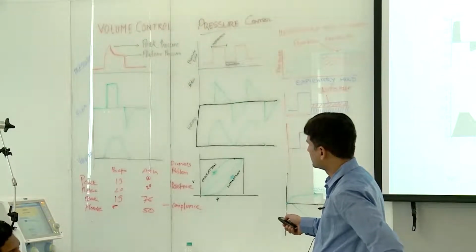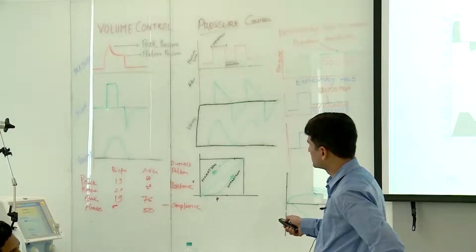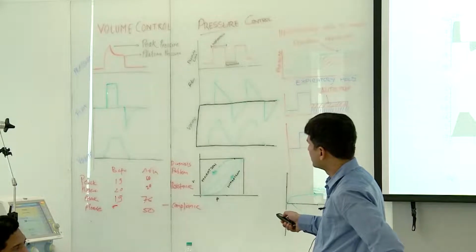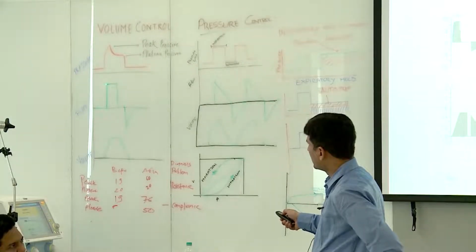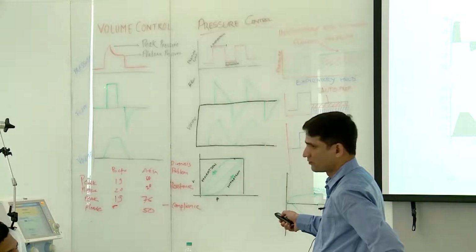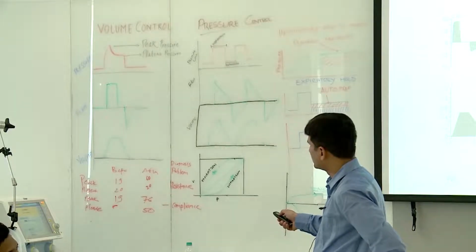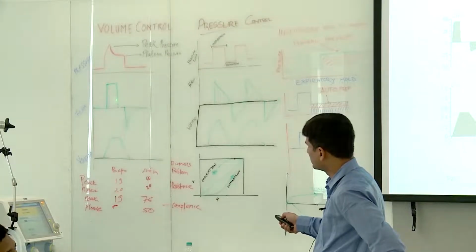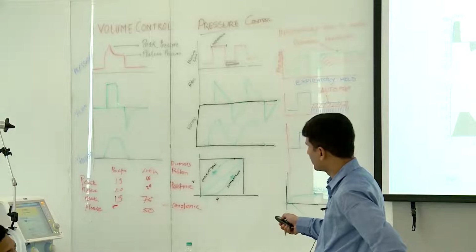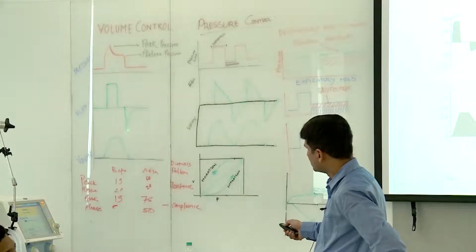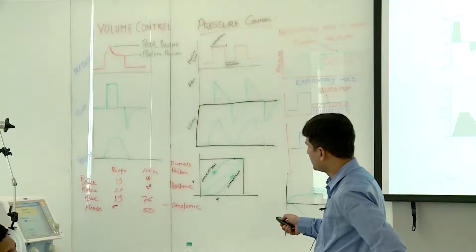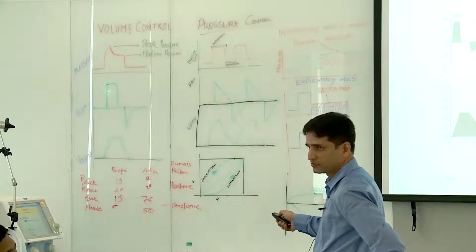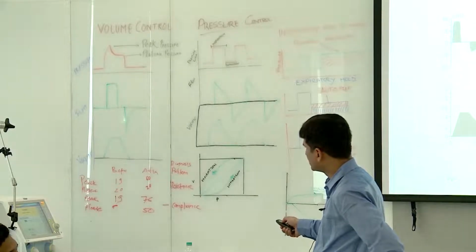Coming to the flow, here the inspiratory valve opens, air rushes inside the lungs and pressure is built up in the system, and as you know in volume control mode the flow is constant. After a certain amount of flow is reached, the expiratory valve opens and the flow again comes back to 0. Then there is expiration. I told you any value above your baseline is positive, meaning the machine is giving a positive flow. Once there is expiration, it is a negative flow.